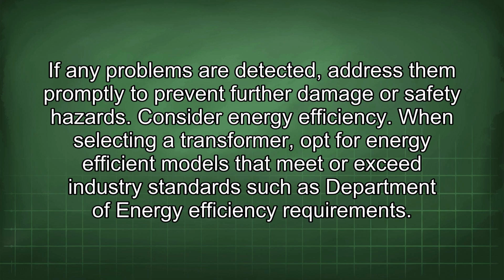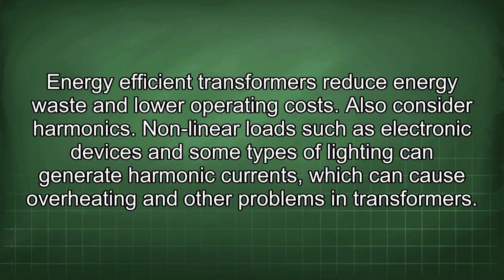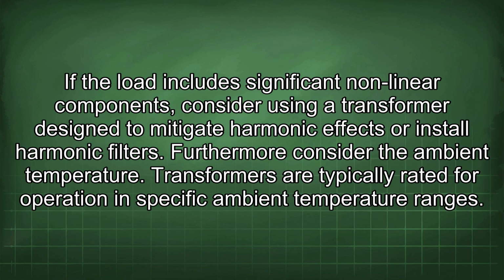Consider energy efficiency. When selecting a transformer, opt for energy-efficient models that meet or exceed industry standards such as Department of Energy efficiency requirements. Energy-efficient transformers reduce energy waste and lower operating costs. Also consider harmonics. Nonlinear loads such as electronic devices and some types of lighting can generate harmonic currents, which can cause overheating and other problems in transformers. If the load includes significant nonlinear components, consider using a transformer designed to mitigate harmonic effects or install harmonic filters.